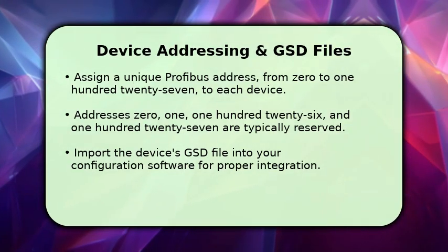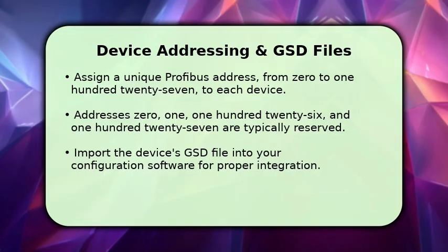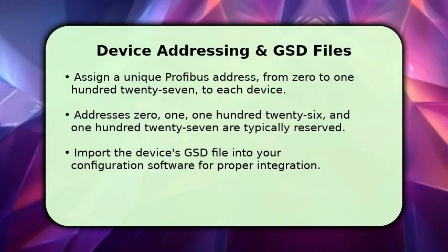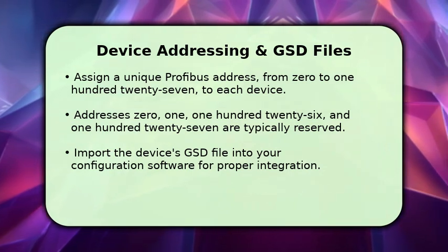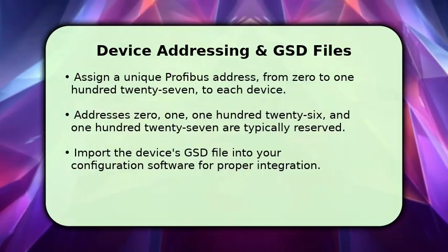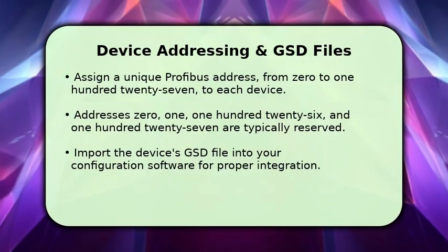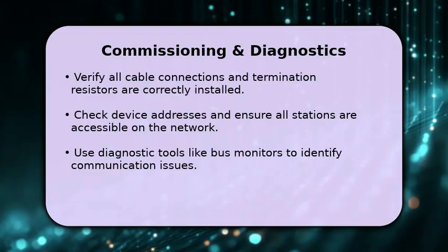You must import the device's General Station Description, or GSD, file into your engineering software. These files are crucial as they describe the device's capabilities, communication parameters like baud rates, and even diagnostic information, ensuring seamless integration and operation. Finally, commissioning and troubleshooting are essential steps.